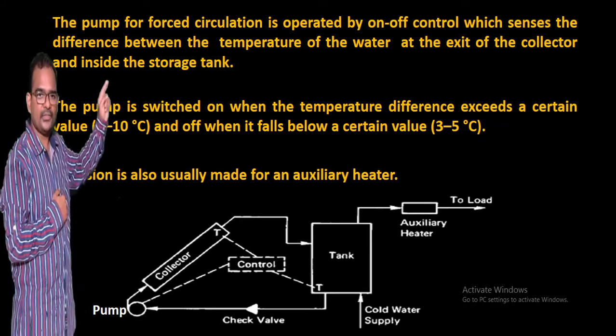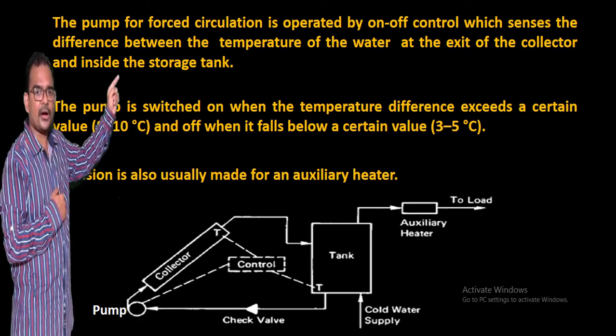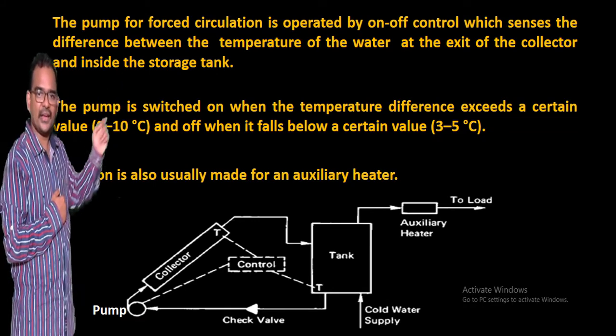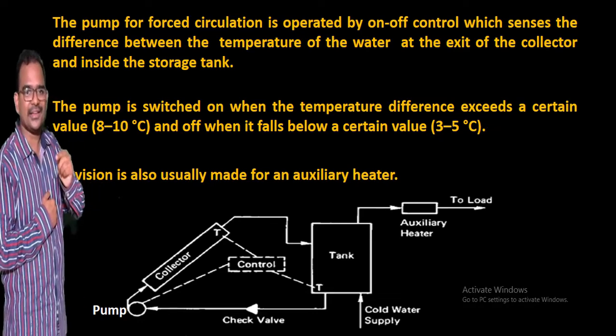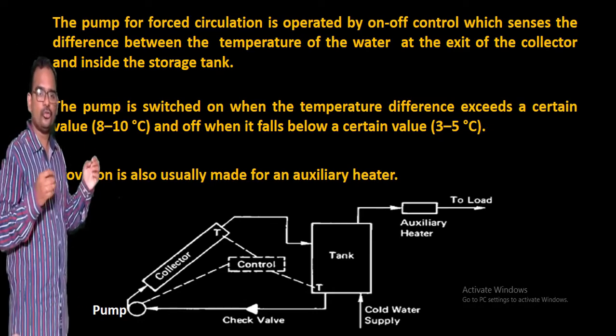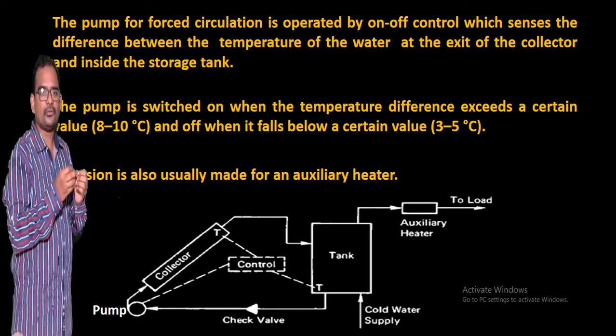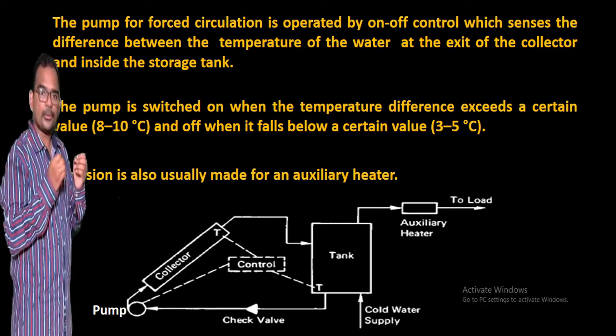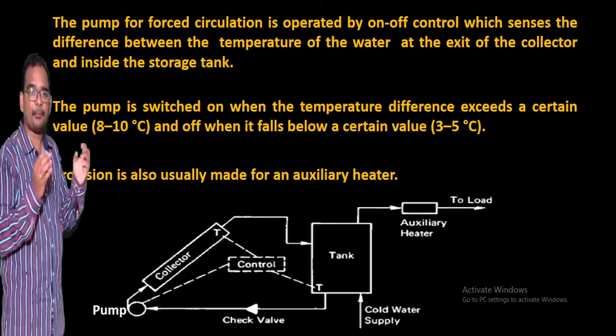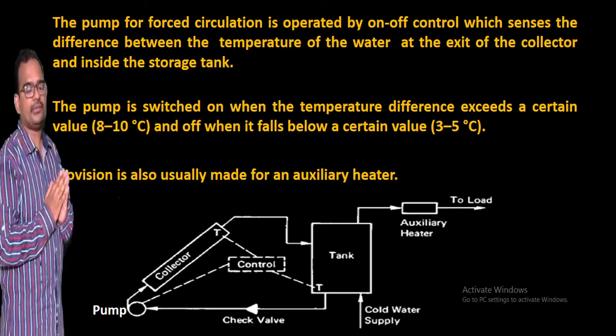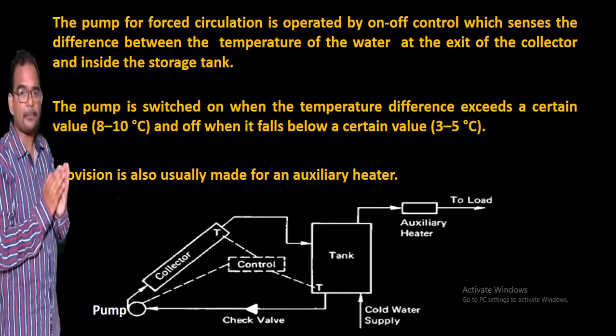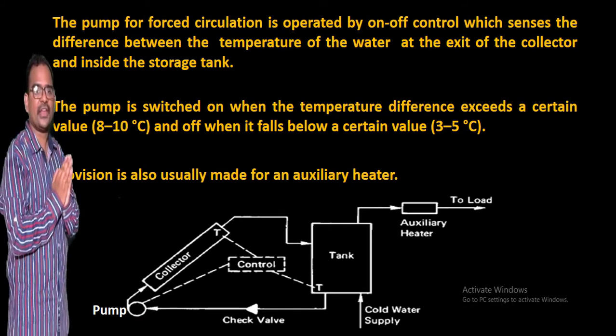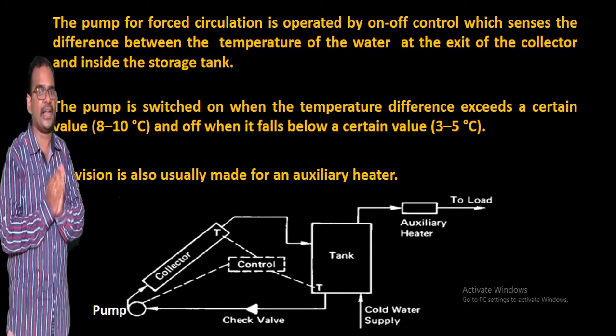The first input is the temperature of the water at the outlet of the collector, and the second input is the temperature of the water inside the tank. Once these two temperatures are measured by means of thermostats or thermocouples, the controller will subtract these two values, that is the temperature at the exit of the collector and the temperature inside the tank.